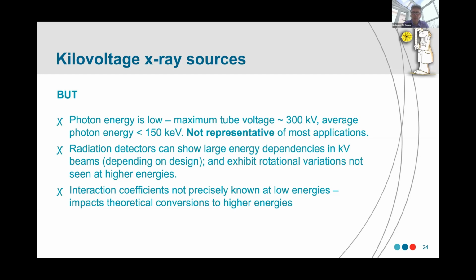We know from extensive measurements that radiation detectors can show large energy dependencies and rotational variations in kV beams that are not seen at higher energies. So if you're establishing performance, you can't necessarily predict from measurements in kV what will happen at high energies where they're going to be used in the end. So it makes prediction of performance more difficult.